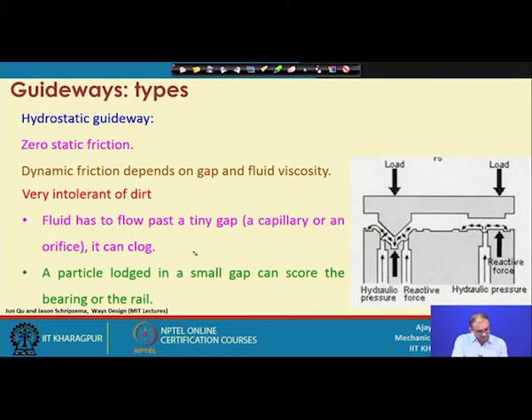Right. So, fluid has to pass through a tiny gap, a capillary or an orifice, and it can clog. A particle lodged in the small gap can score the bearing or the rail. Now, there is another problem, because by chance the particle size may be smaller than 15 micron. First thing, it will not clog. So if the particle is smaller than 15 micron, then no clogging.